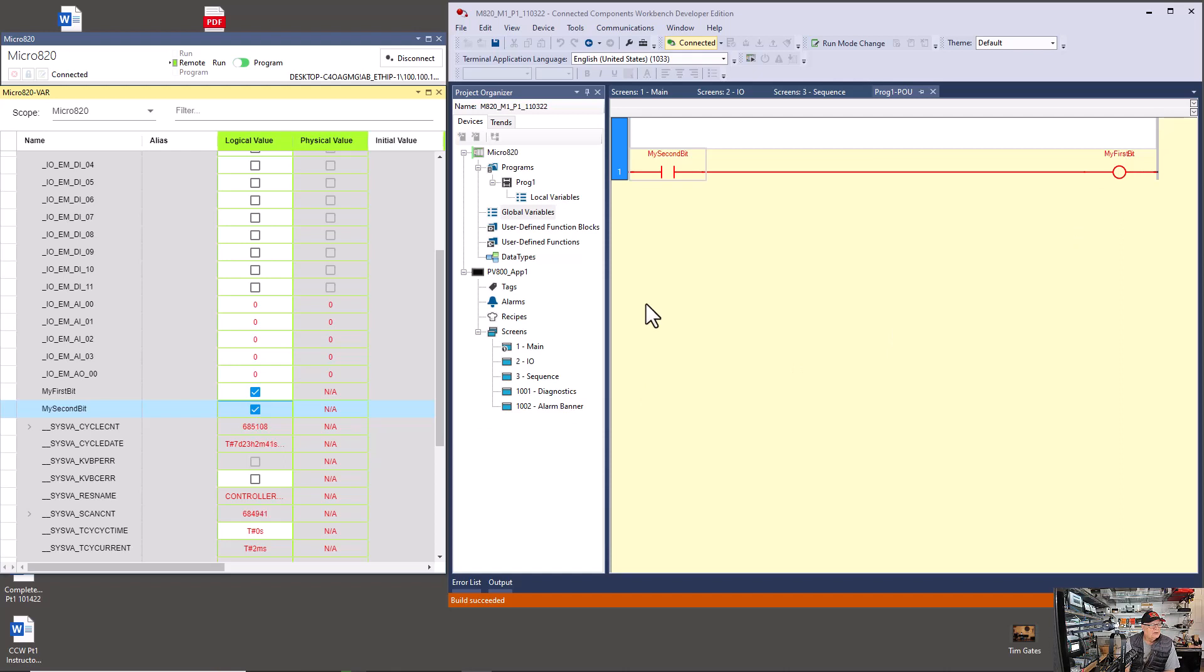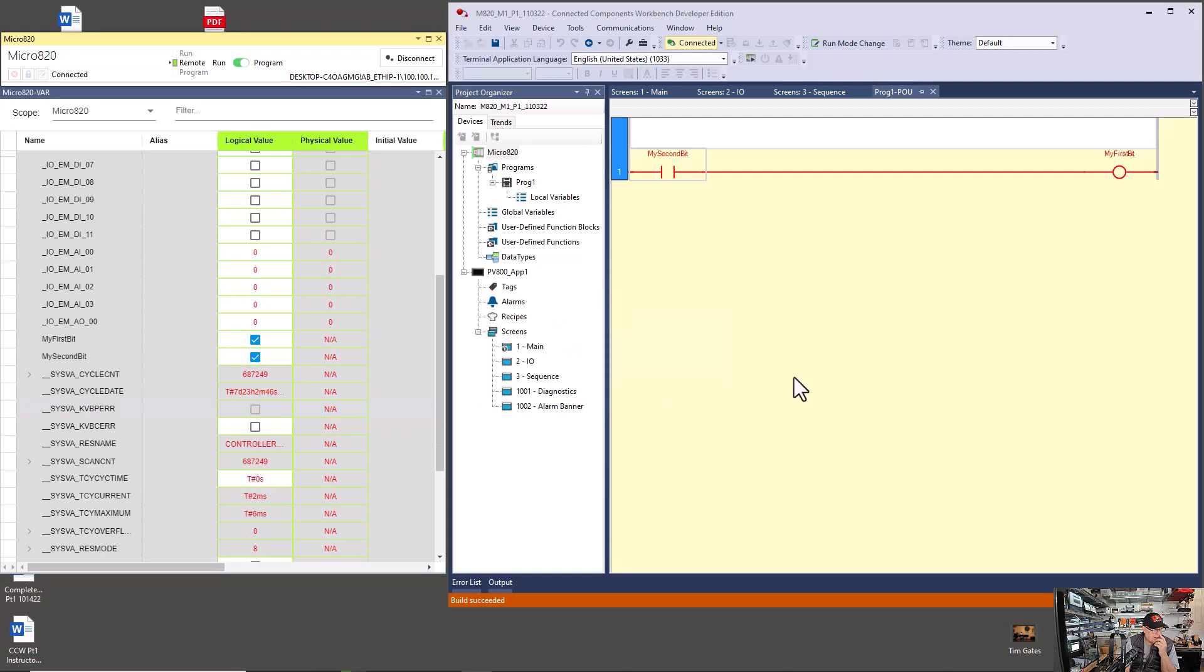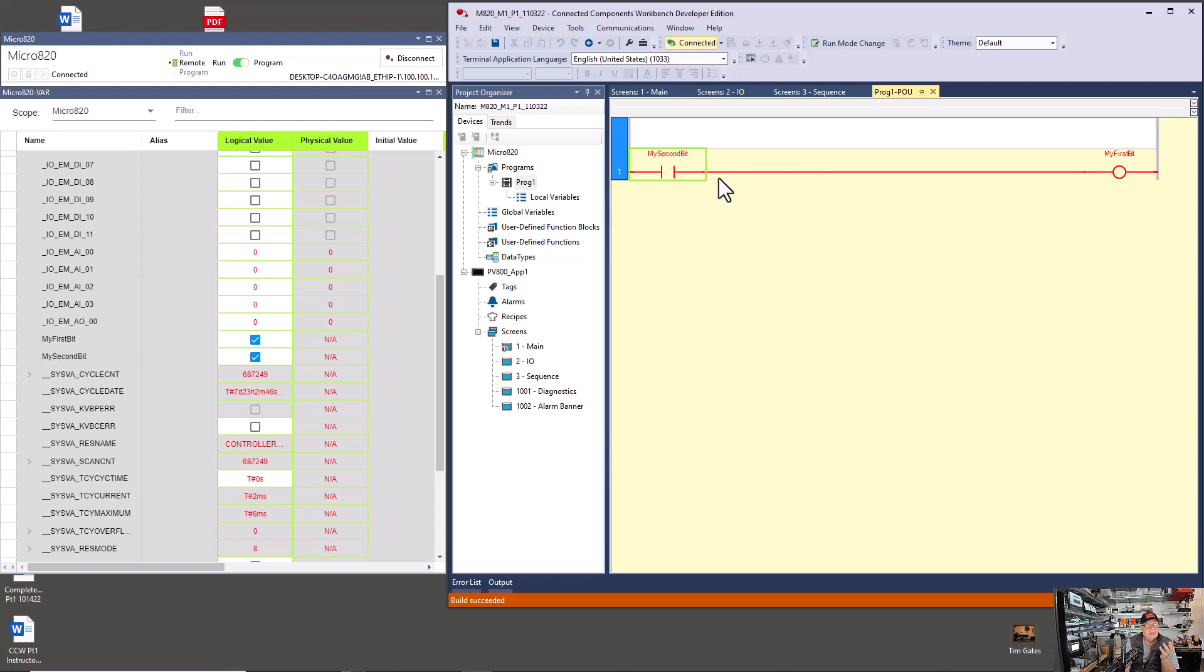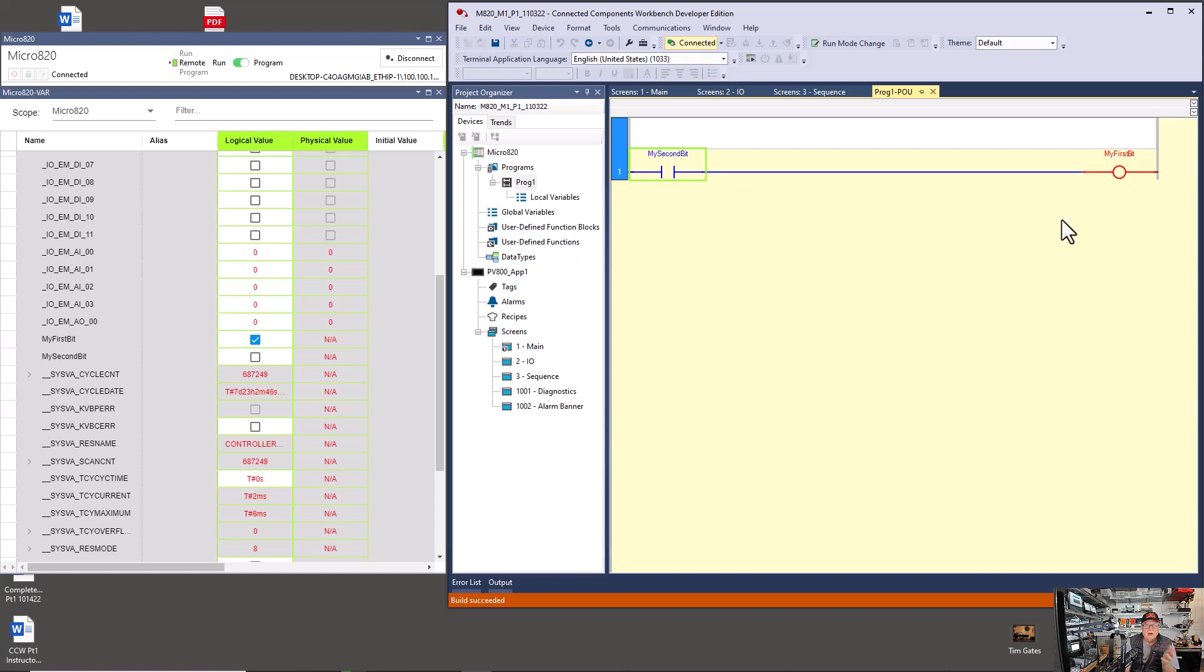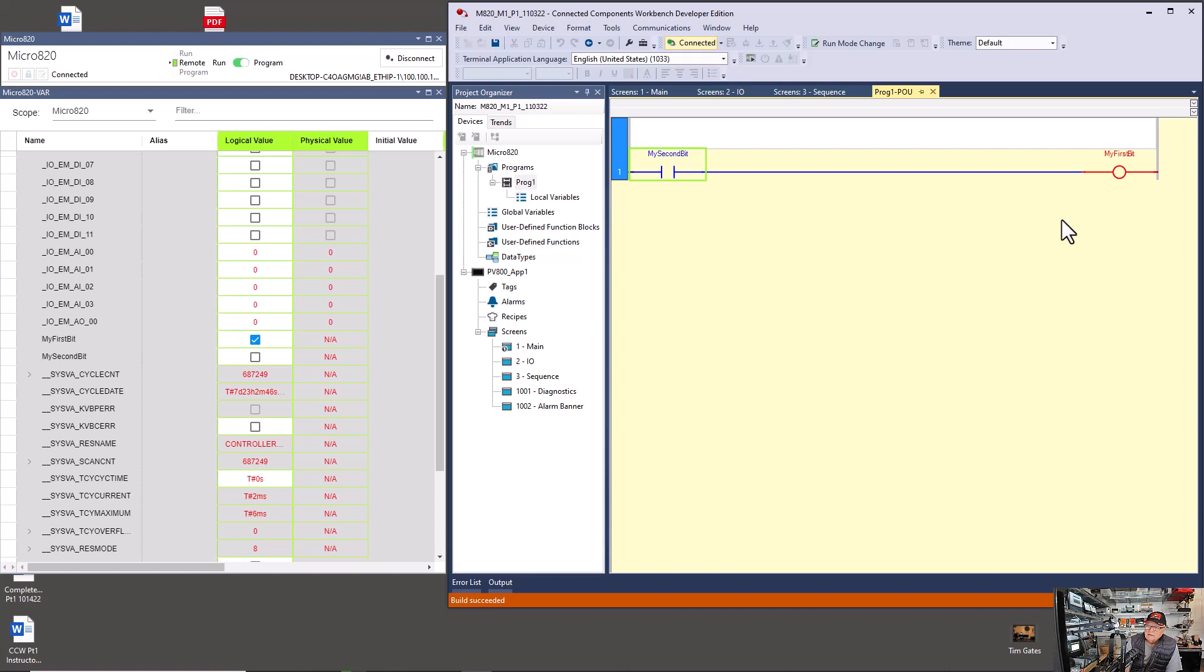I'm going to turn off, well, better yet, I'm going to put it in the program mode. And of course, my panel view screen still shows the same thing, but I'm going to toggle off my second bit. But see, we're not running. So this rung of logic is not telling my first bit that it should be on or off. It just stays in the last state. I look over my panel view screen and sure enough, my second bit is off and my first bit is on. We're going step by step here, developing your ability to pick what kind of screen objects you need to display what the operator needs to see to improve and enhance their ability to operate the machine. That's the whole idea of an HMI. It is not for you to express your artistic desires and acumen. It is to make it very clear to the operator what they need to do, the information that they want. Less is more. The less it's on there, the more quickly they're going to figure out what's going on.